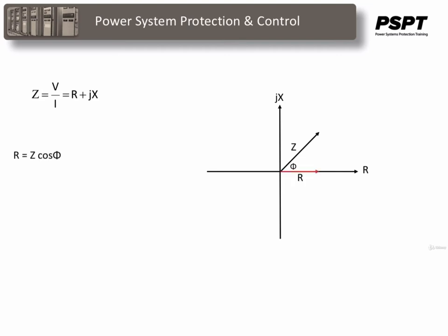R is the impedance Z times cosine of the angle. X is equal to the impedance times the sine of that angle. Theta is positive if I lags V, and negative if I leads V. Thus, V and I can be converted on an R-X diagram. The family of impedance relays, or distance relays, can offer a wide range of characteristics which we are about to look at.